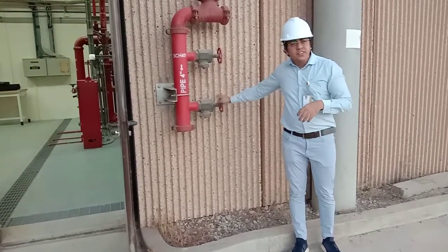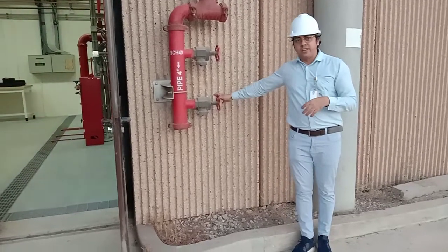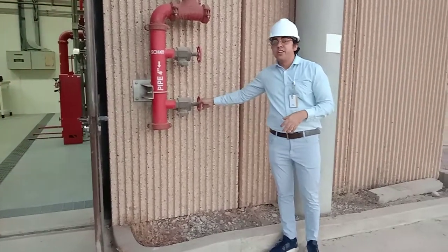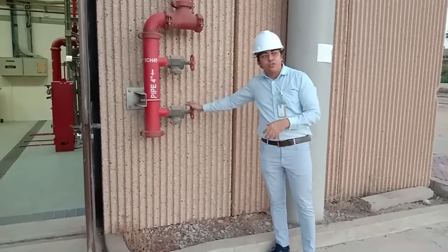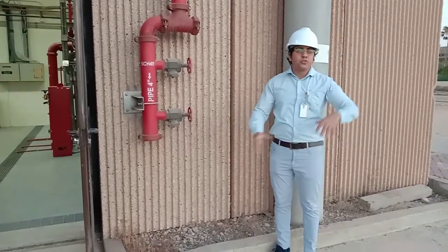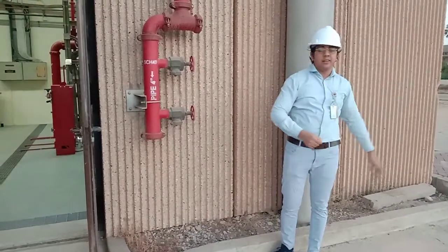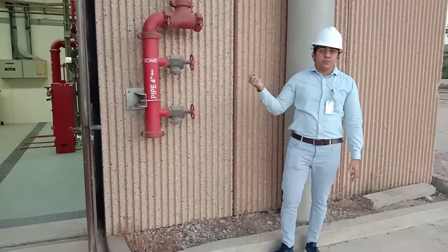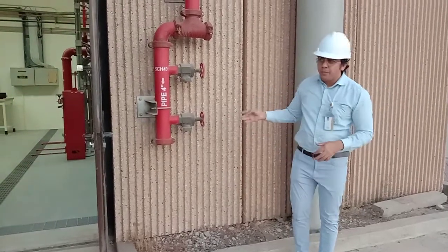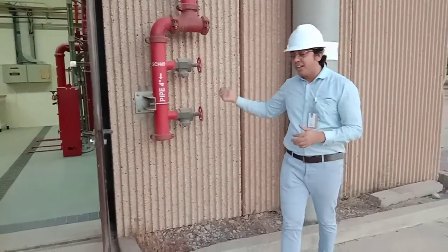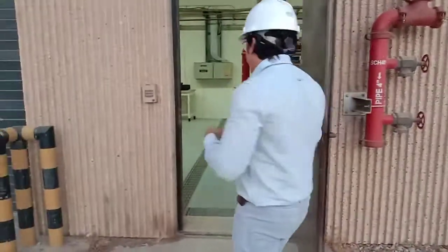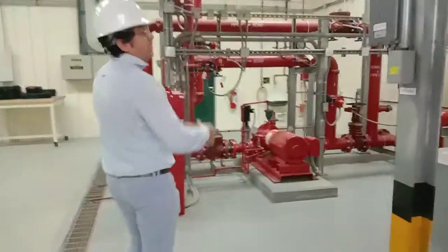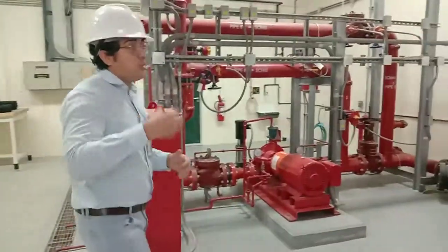But again, this is sometimes not environmentally friendly. We have to discharge a large quantity of water into the atmosphere. Suppose your pump is of 3000 GPM, right? And you have to run your pump for 10 minutes. So the discharge will be so much, right? It will flood the complete area, or maybe you have to note down your pressure and those ratings. Even in a short duration of time, the area will be flooded. So we have some other options to save water, right? Saving water is the most general talk in recent days. Why should you waste water for doing a flow test?